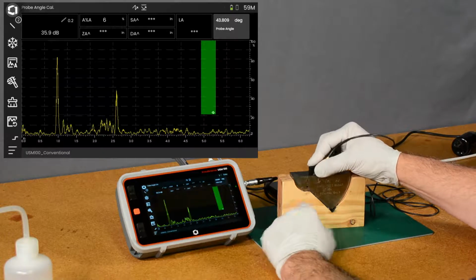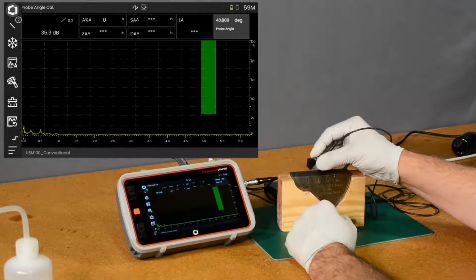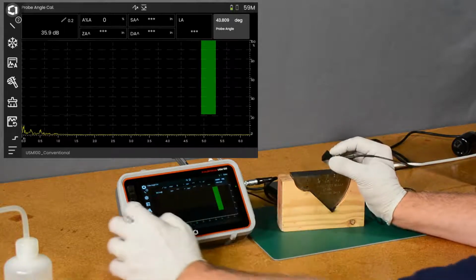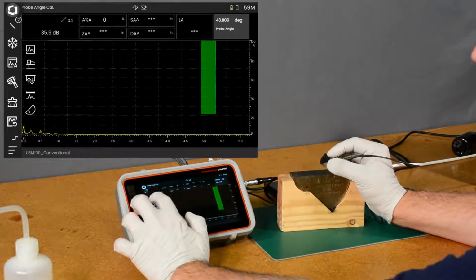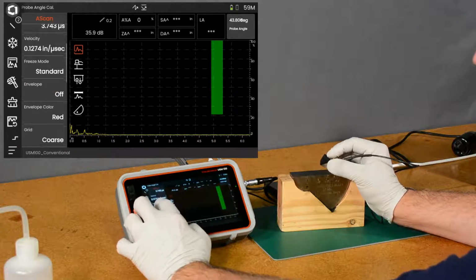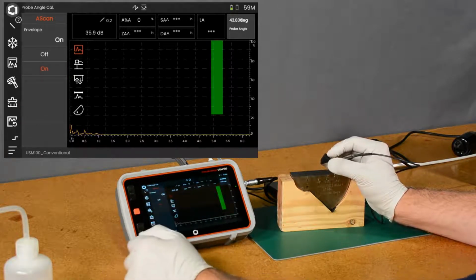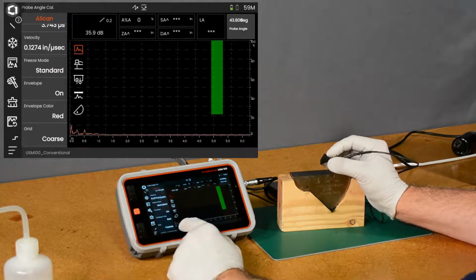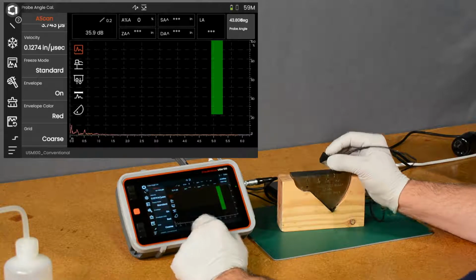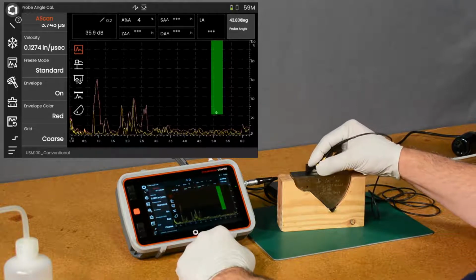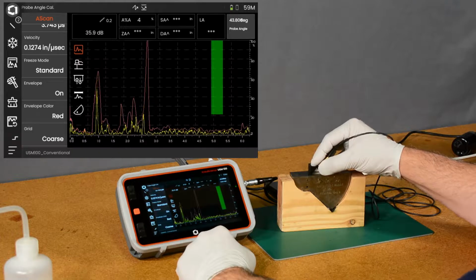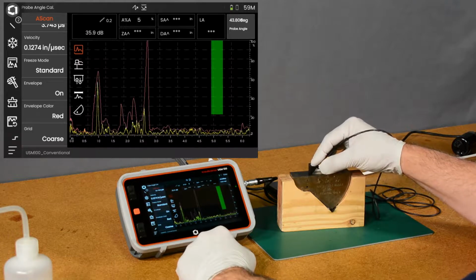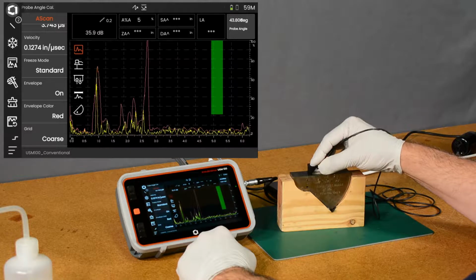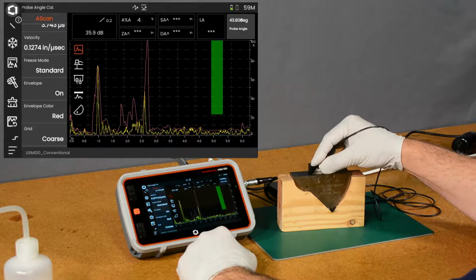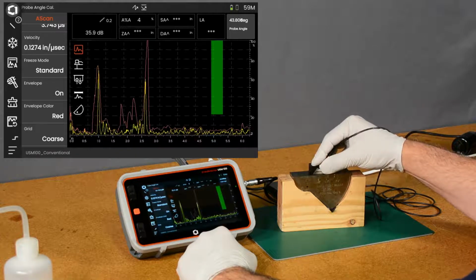Okay. Now, as we mentioned, finding the exact peak location is a little fidgety with the probe. So let's make it easier. Let's go to our A-scan menu, and we're going to come down here and turn envelope mode on. Okay. What envelope does, you notice the A-scan now is red on the screen. And as I put my probe down and move around, our peaks draw another trace in red. Our live A scan is in yellow. I can use that to assist me in finding where I have actually peaked up that probe.